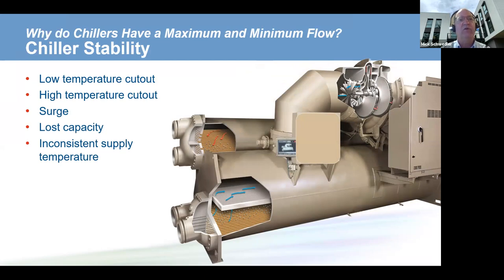We get closer to that transitional area that we saw in the previous graph. And what happens is when our heat transfer gets poor, we get a higher approach temperature between the leaving water temperature and the refrigerant temperature. So on the evaporator, that can cause us to get to a low temperature in the evaporator and have to turn the chiller off. It can also get to a high temperature in the condenser and cause the chiller to get into a place where it's not going to operate well.